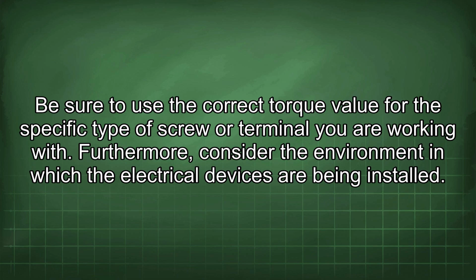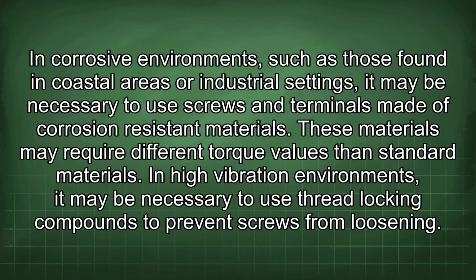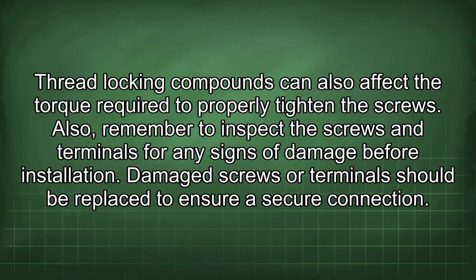Furthermore, consider the environment in which the electrical devices are being installed. In corrosive environments, such as those found in coastal areas or industrial settings, it may be necessary to use screws and terminals made of corrosion-resistant materials. These materials may require different torque values than standard materials. In high-vibration environments, it may be necessary to use thread-locking compounds to prevent screws from loosening. Thread-locking compounds can also affect the torque required to properly tighten the screws.